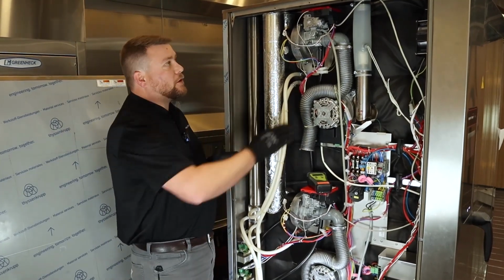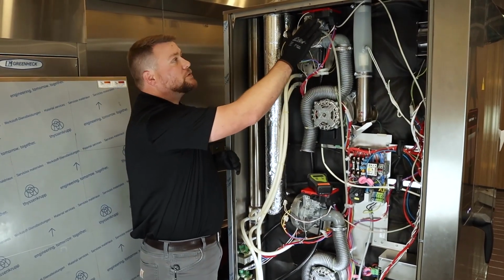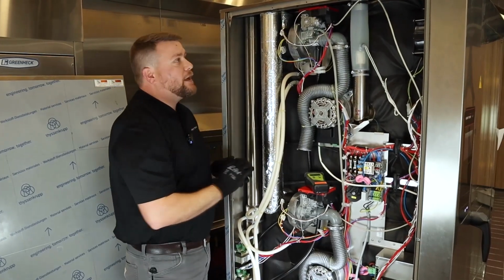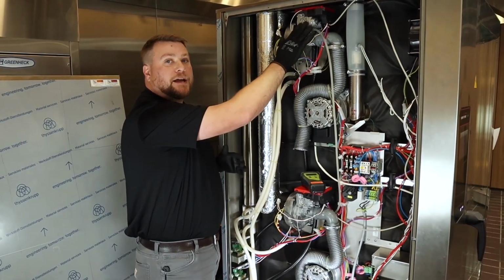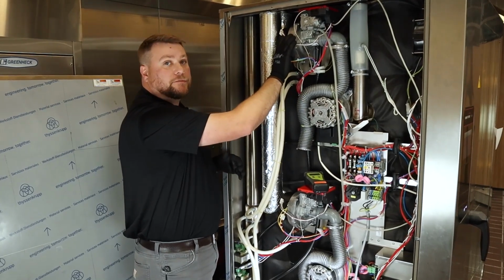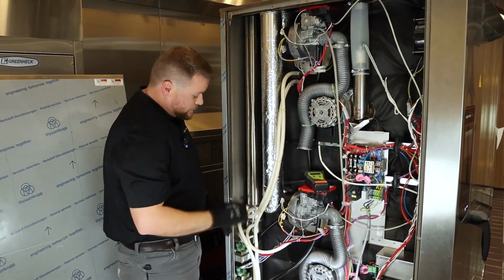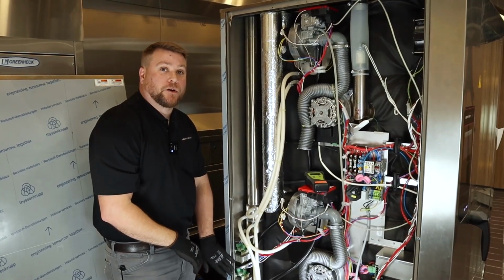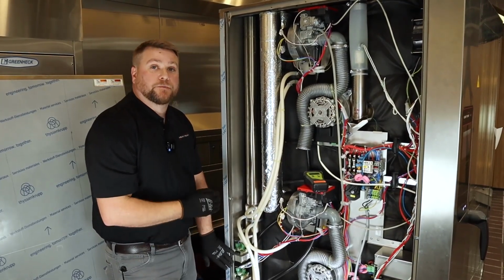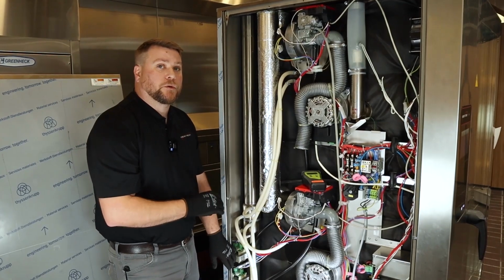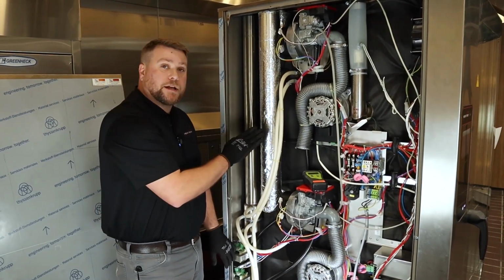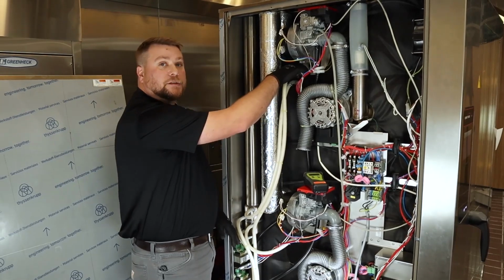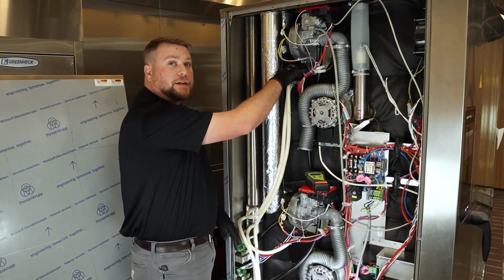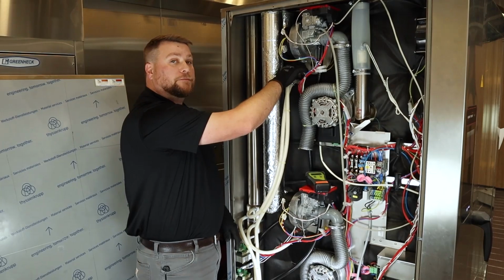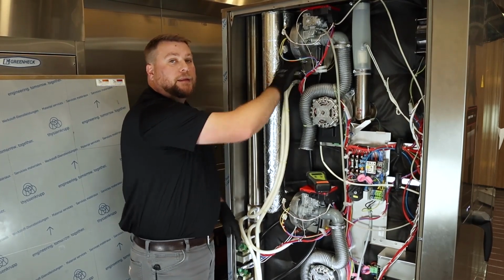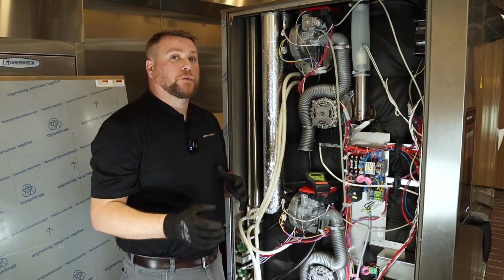So components involved are going to be, as I mentioned before, our ignition module, which is located right here, this red and black cover, and then right underneath of it, we're going to have our gas valve, as well as our combustion fan for the blower. And then we're also down here, as I mentioned before, we're going to have our transformer that drops the voltage down from line voltage down to 24 to 28 volts AC for our glow electrode. And then that glow electrode is going to be inside the combustion chamber right underneath the fan here, as well as also our flame sensor is going to be in there as well. Now, so those are some of the items that are involved with the gas heat system.